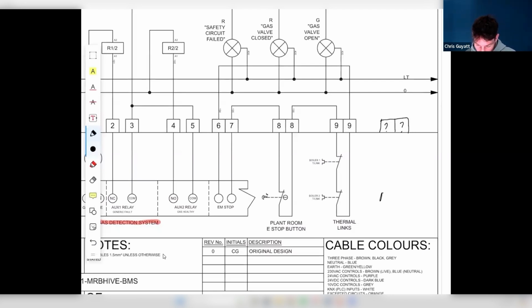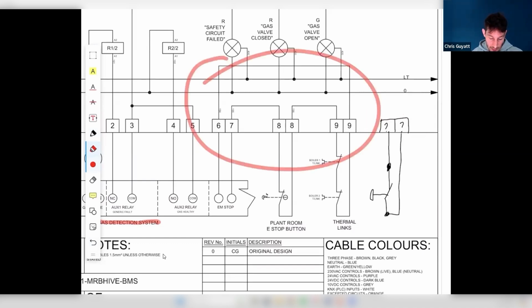Forgive my drawing. I would install the e-stop at the reception area. So that's on the wall. Then I'm going to wire this e-stop in. So I'm connecting my 2-core cable here, back to the panel, and here, back to the panel. So that's out in the field now. Now we just need to work this into this series circuit that we've just talked about, which then ultimately goes back to the gas detection system.